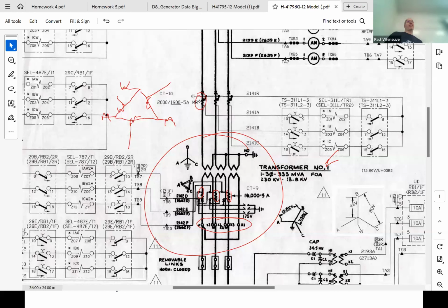Well, maybe that's not that rare. I've been doing this for almost 35 years and I've never seen them. There are advantages to it, but there's really no need to bury them because you can get the information you need from the delta, from the CTs on the bushings. So there isn't really a big advantage - it's got to be delta. There's no advantage at all to having them buried if it's on a Y.